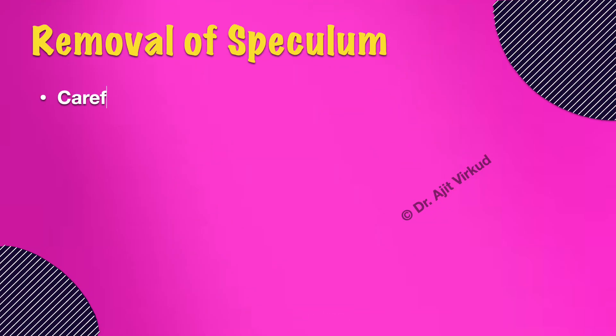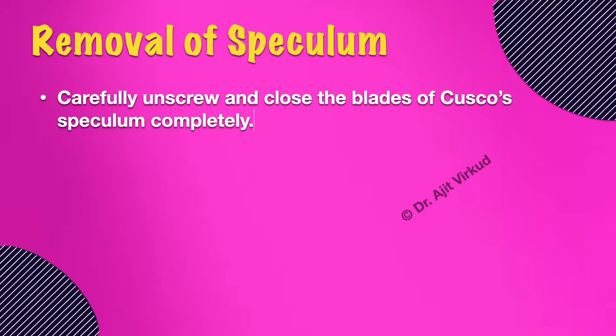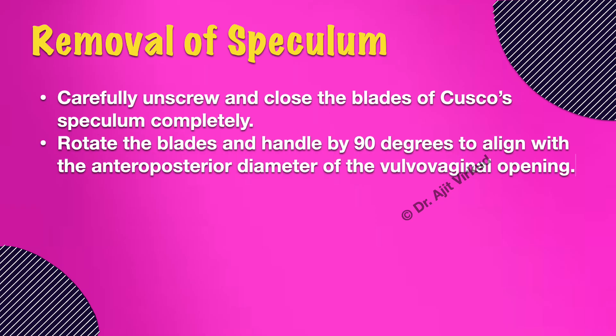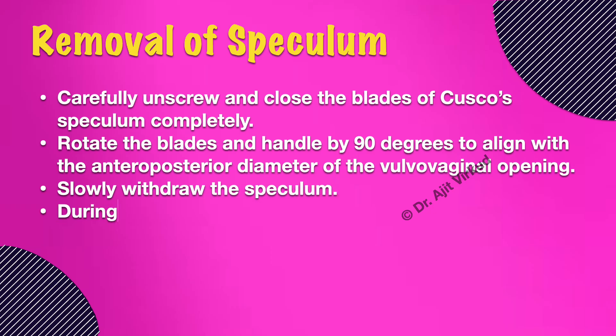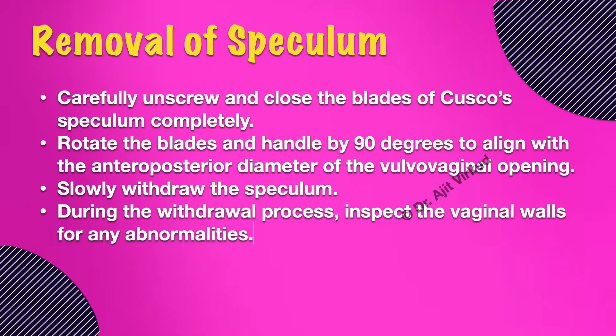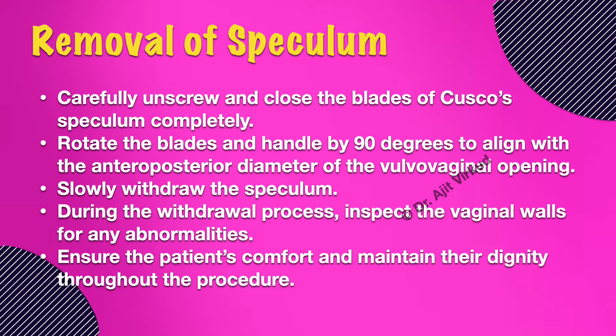Carefully unscrew and close the blades of Cusco's speculum completely. Do not allow the lax vaginal walls to get pinched between the blades when closing them. Rotate the blades and handle by 90 degrees to align with the anterior-posterior diameter of the vulvovaginal opening. Slowly withdraw the speculum. During the withdrawal process, inspect the vaginal walls for any abnormalities. Ensure the patient's comfort and maintain her dignity throughout the procedure.